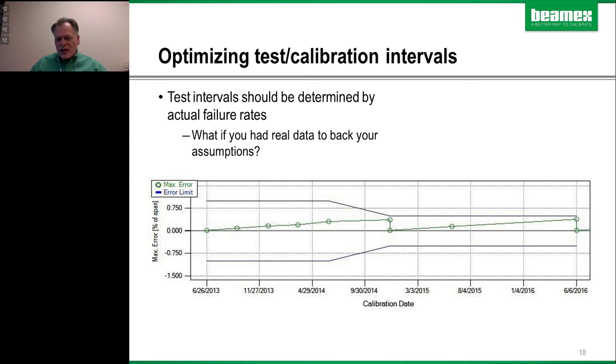And here's an example. So here's a test that was done every 6 months, and it looks like the pass-fail was 1%. And after 2 years or more of data collection, the interval was changed maybe to 9 months, and the tolerance was tightened to 0.5%. And there still was no failure. An adjustment was made. It was brought back to true, same interval. Look at that same angles there. And then finally, we drifted out.